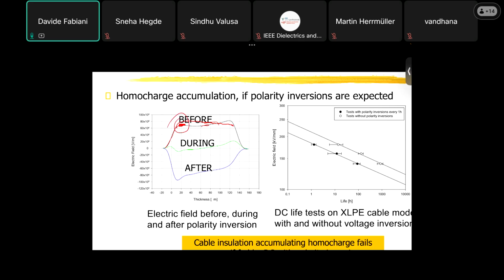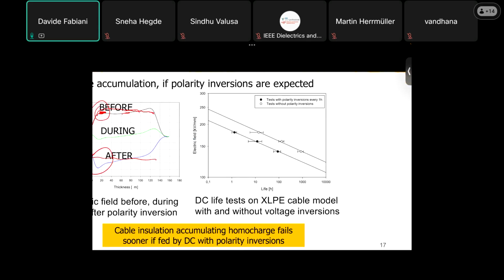and you can see that the field here is lower. Then you apply a polarity reversal, which is, of course, sometimes requested to invert the power flow in your cable. If you apply the polarity reversal, the problem is that what is homocharge becomes heterocharge once you have reversed the polarity of your electrodes. And what you can see here is that after polarity reversal, the electric field in correspondence of this electrode becomes very high. And this can create, of course, an extra stress to your insulating material. And this is more evident when you do endurance tests, life tests on your material.